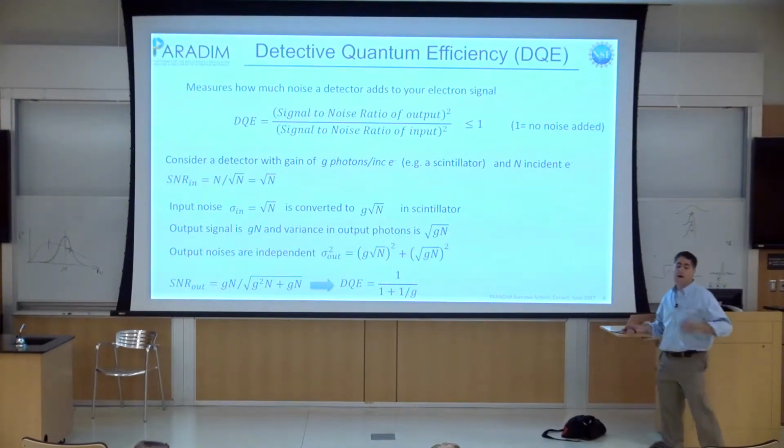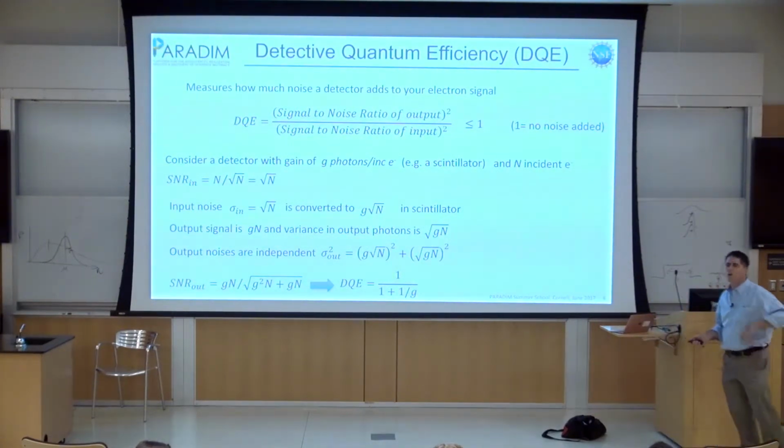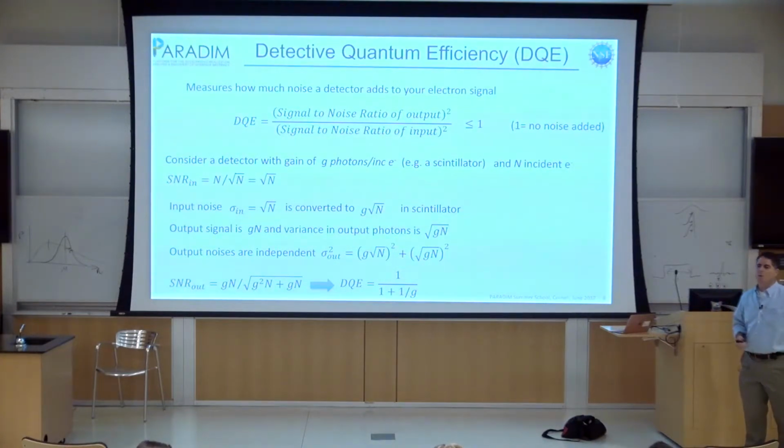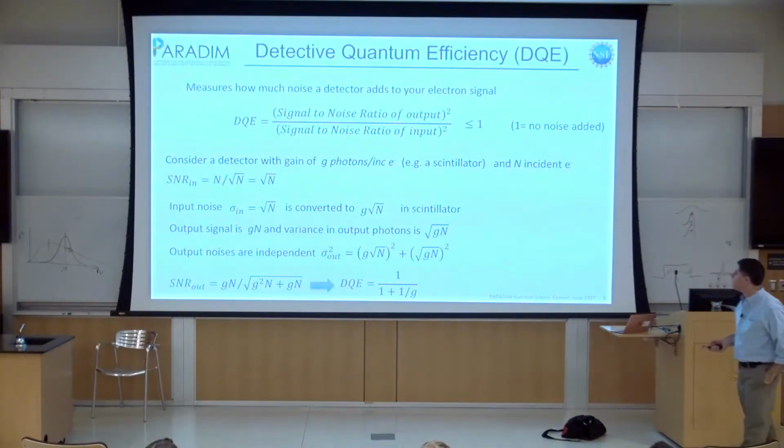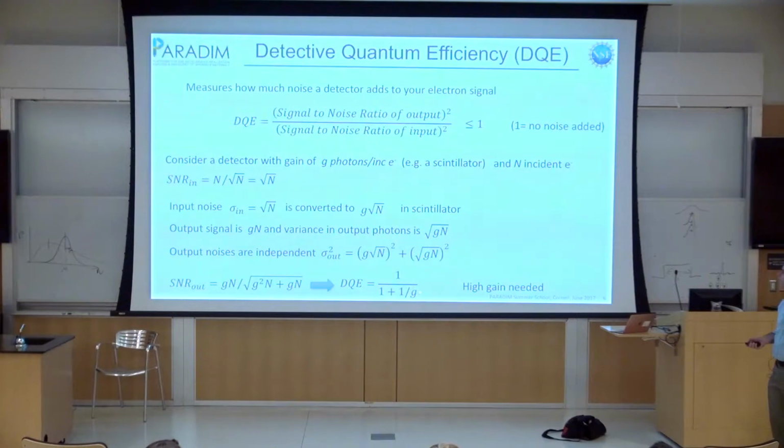And that often means a high beam energy. So scintillators work well for high voltages, which is all of TEM. They don't work as well for SEM, where you might only be getting 5 or 6 photons out for each incident electron. But they're pretty good for TEM.